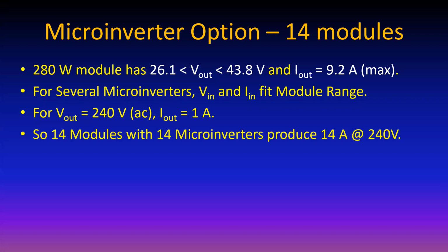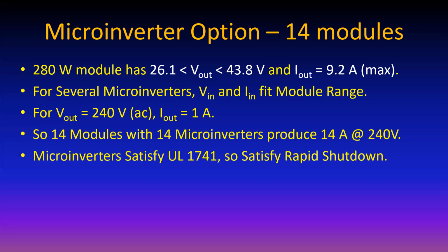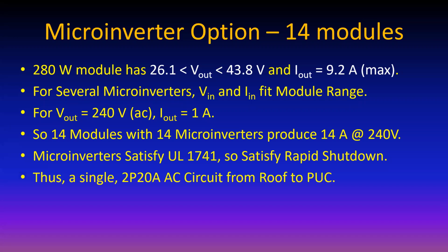And you find that out on the specification sheet. The microinverter's is 2 pages long, as is the module's and almost every other piece of equipment's, a 2-page spec sheet that gives all the performance numbers. So 14 modules, 14 microinverters at 1 amp apiece, you get 14 amps at 240 volts. Microinverters themselves satisfy UL 1741. So if the utility goes down, the microinverters go down, and there's no more power leaving beyond the modules themselves because the microinverters are mounted directly underneath each module. That's very nice because it doesn't add any additional cost to the system to satisfy rapid shutdown.